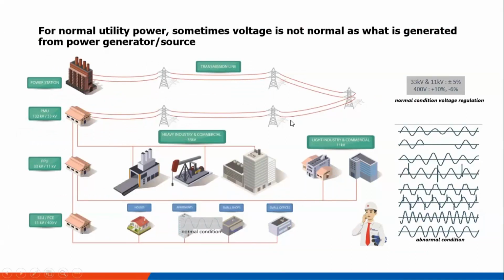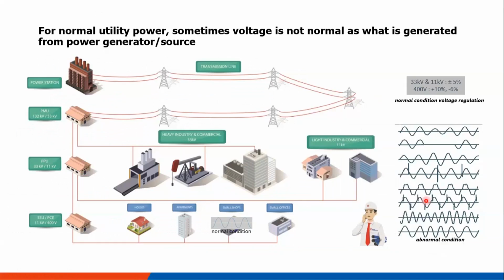Okay? In the ideal case. However, sometimes the voltage is not normal. It's what is generated from the power source due to certain things. So the normal condition will be a nice sinusoidal, but the abnormal condition will be the sinusoidal on the right here. Okay, there are many types of non-smooth sinusoidal, and this is considered abnormal condition. And the normal condition for voltage is like this: 33 kV and 11 kV is plus minus 5%, and for 400 and 230 is plus 10 and minus 6%. So in the ideal case, a nice sinusoidal is transmitted from the power plant to the transmission line and distributed nicely to every customer connected to the grid.